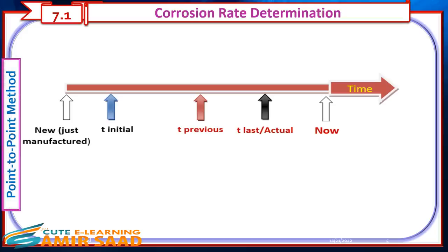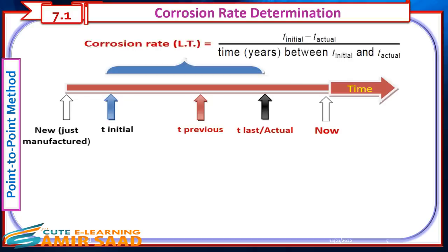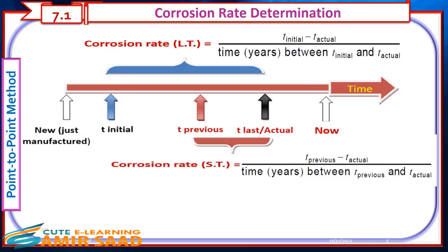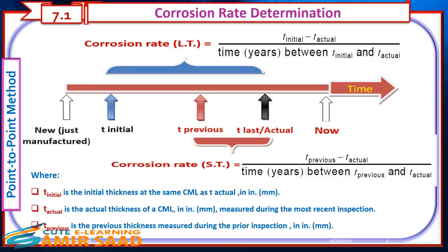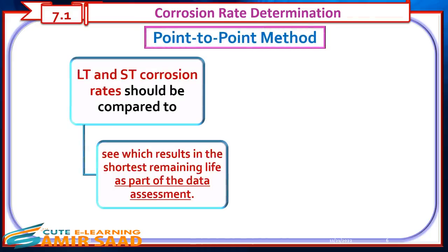Corrosion rate calculations by the point-to-point method are illustrated in the figure. The long-term corrosion rate equals T-initial minus T-actual, divided by the time between T-initial and T-actual. The short-term corrosion rate equals T-previous minus T-actual, divided by the time between T-previous and T-actual. Where T-initial is the initial thickness at the same CML as T-actual, T-actual is the thickness measured during the most recent inspection, and T-previous is the thickness measured during the prior inspection. The long-term and short-term corrosion rates should be compared to determine which results in the shortest remaining life.